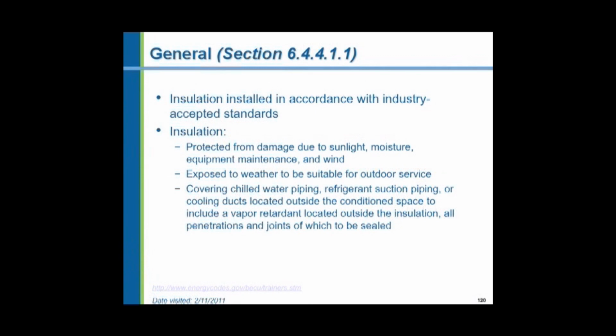If you have ductwork outside, and this used to be the case that there was not space inside a ceiling for ductwork, an air conditioning apparatus and ductwork might be outside on the roof. I've seen a number of buildings that way. It was very difficult to find an insulation protection system that could withstand ultraviolet light for years at a time in temperature extremes. So many systems now are being designed with internal insulation in the ductwork, and the ductwork is soldered watertight. And the zinc-coated galvanized ductwork withstands ultraviolet light quite well and withstands rain and the weather and the heat in the summer and the cold in the winter. So the galvanized ductwork, soldered watertight, is a very good weather protection with internal insulation. However, water piping on the outside of the building cannot be insulated internally. So if you have piping outside, going to a rooftop chiller, for instance, you have to protect this piping insulation, and typically they're now doing it with an aluminum jacket, sealed tight over the outside of the insulation.